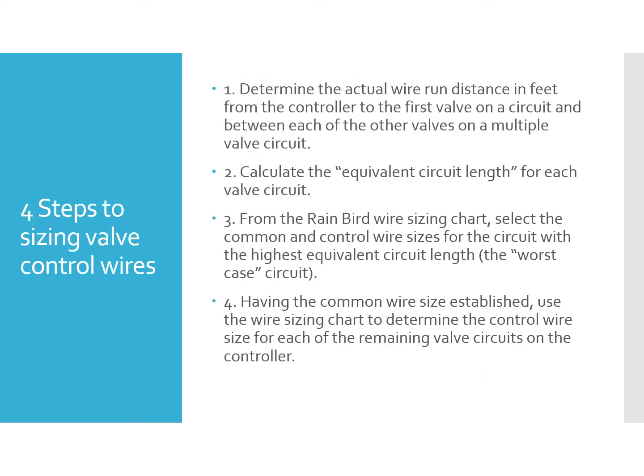Okay, so now we're going to talk about 4 steps that Rain Bird has lined out in this textbook on determining the size of your valve control wires. So these are the 4 steps. 1, determine the actual wire run distance in feet from the controller to the first valve on a circuit and between each of the other valves on a multiple valve circuit. 2, calculate the equivalent circuit length for each valve circuit. 3, from the Rain Bird wire sizing chart, we'll select a common and a control wire size for the circuit with the highest equivalent circuit length, or basically the worst case scenario. And 4, having the common wire size established, use the wiring chart to determine the control wire size for each of the remaining valve circuits on the controller.